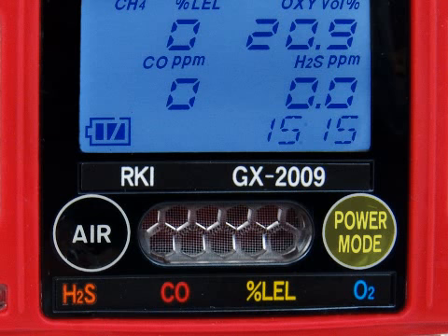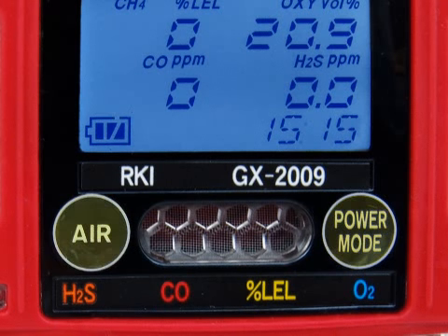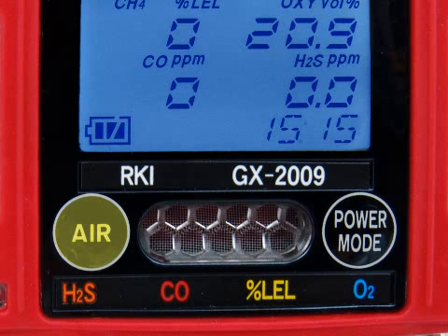The power mode button will turn on the unit as well as the LCD backlight. It is used to scroll through the display mode, reset gas alarms, and enter calibration and setup modes with the air button. It is also used to select displayed items and parameters and to save adjusted parameters. The air button is used to perform a fresh air adjustment, adjust or change parameters, and also turns on the LCD backlight.